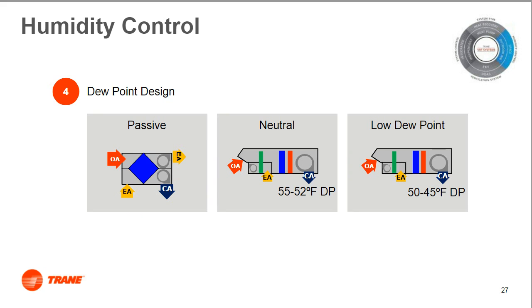Lastly, dew point design should be a big consideration when delivering outside air into a space. These specific methods do include passive cooling with the use of an energy recovery ventilator, neutral cooling, which uses the 55-degree rule of thumb to supply conditioned outside air to a space, and the low dew point method, which in high humidity environments may be required in order to meet strict relative humidity set points or comfort cooling. Depending on your design environment, addressing humidity concerns does not have to be difficult.